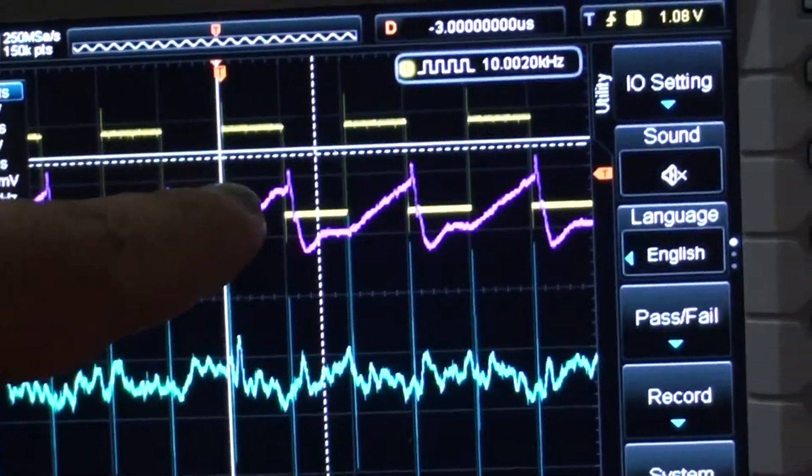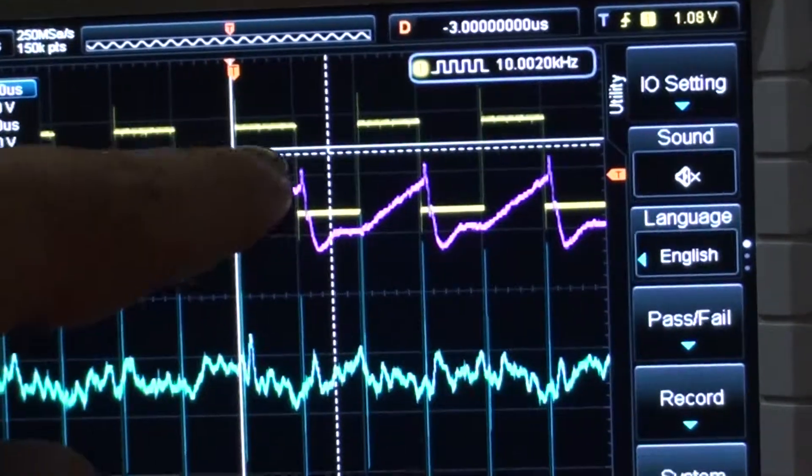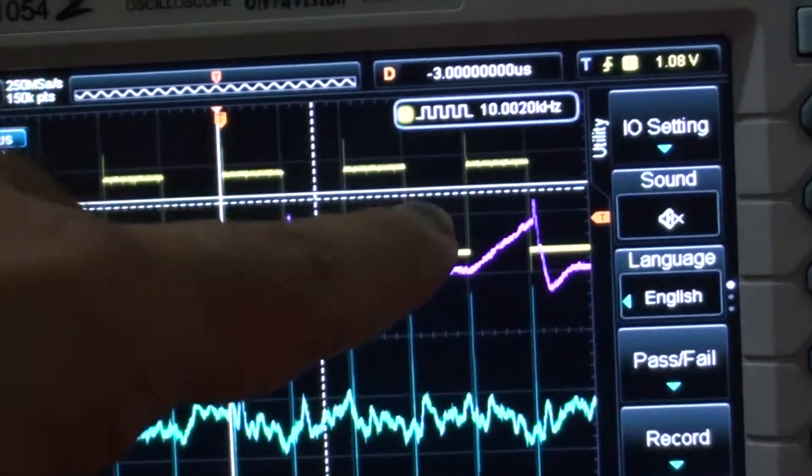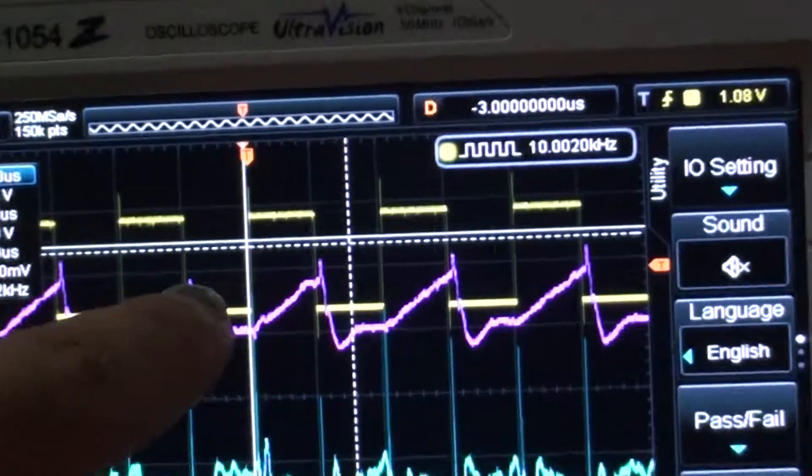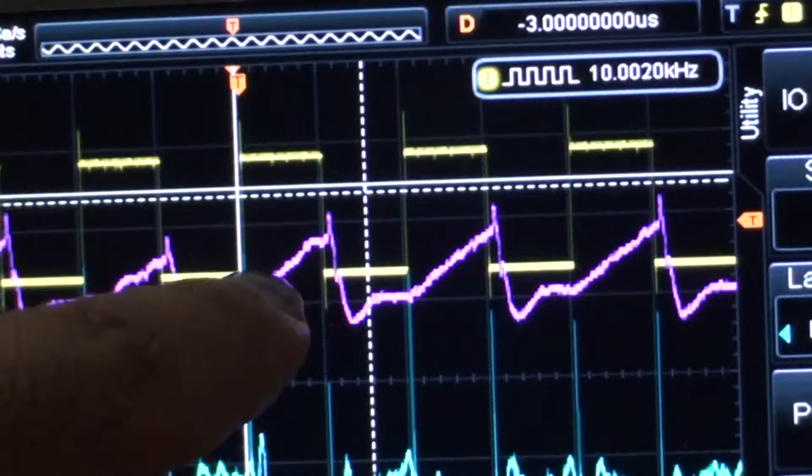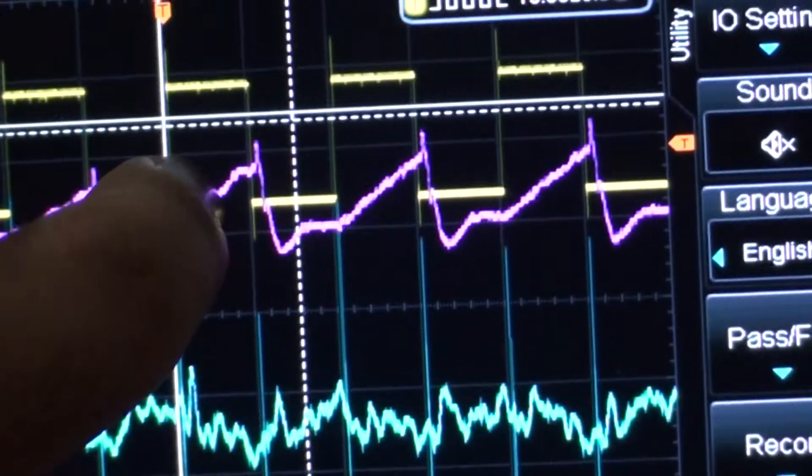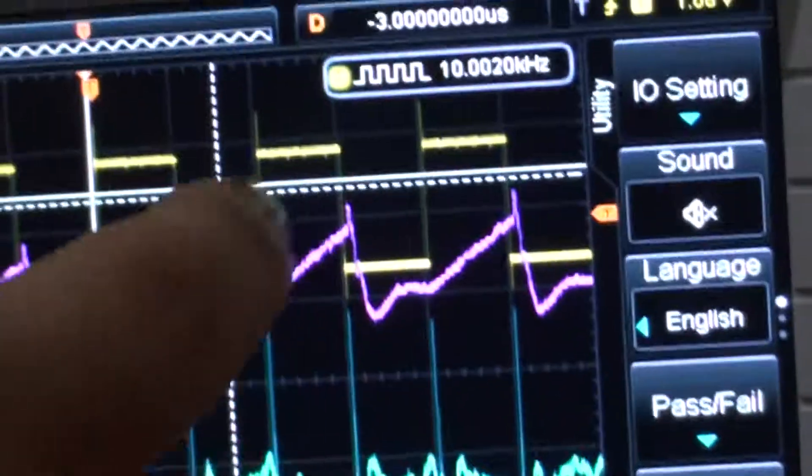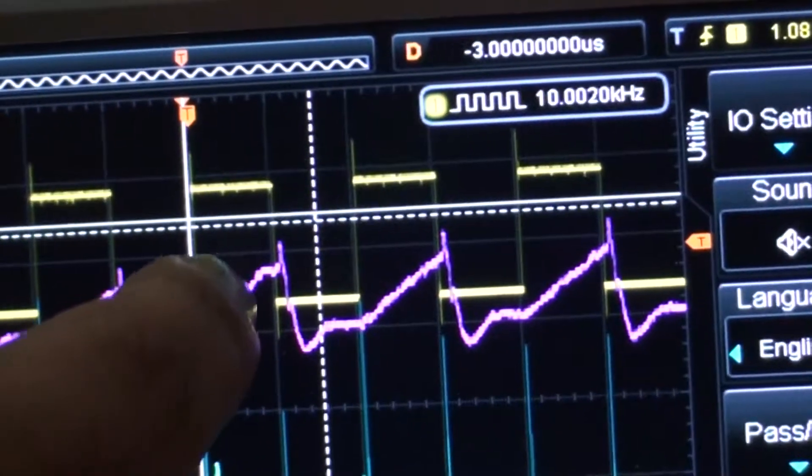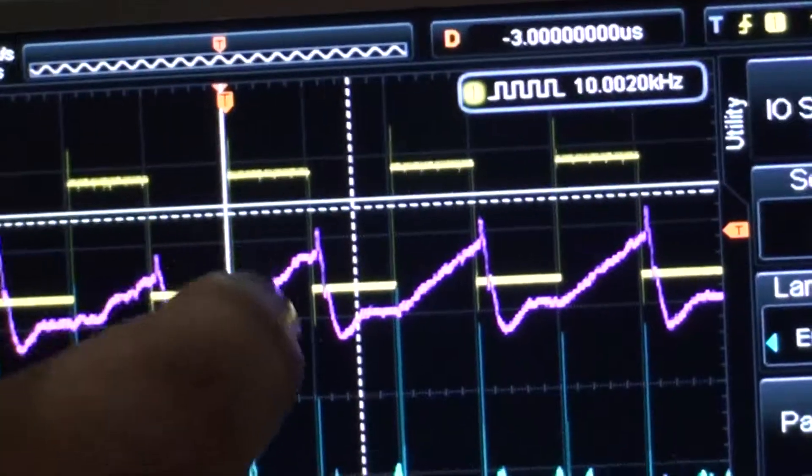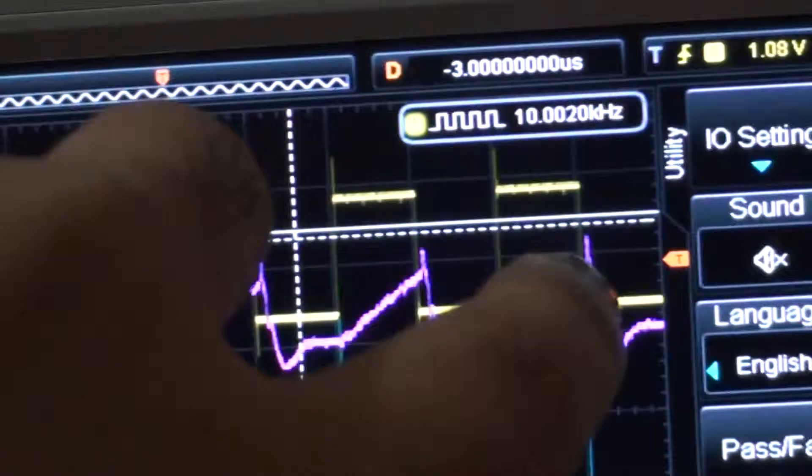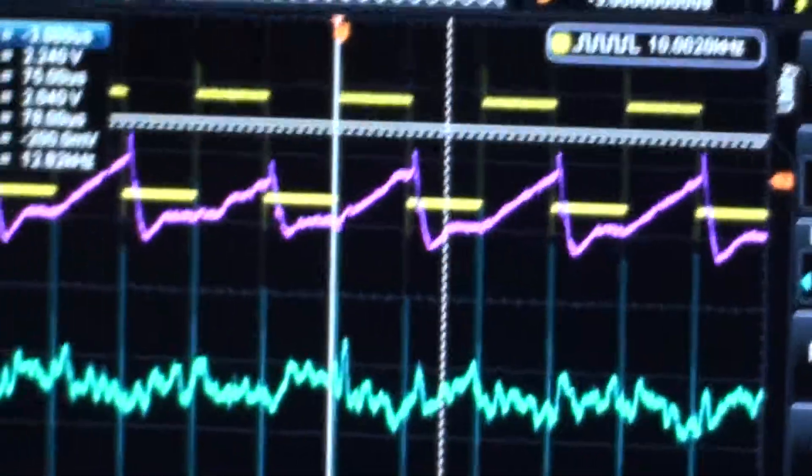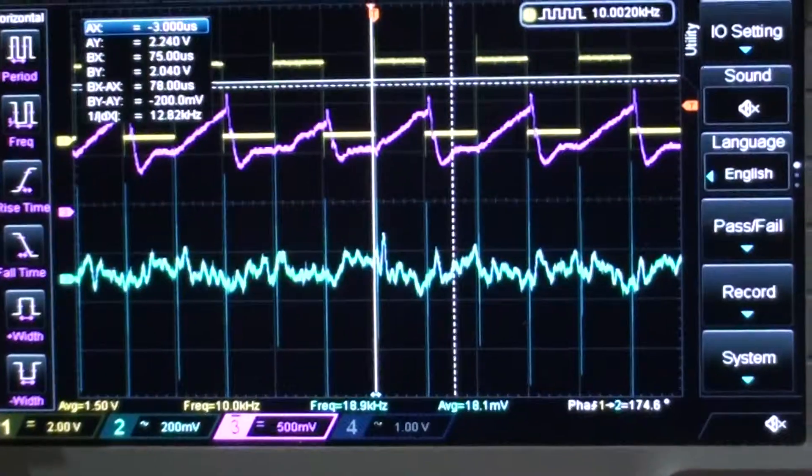Now how do you eliminate the noise or eliminate the PWM frequency that is riding on this, going up and down? Typically we do a synchronized measurement—that is, the measurement is done somewhere in the center, right at this point. If you synchronize the current measurement with respect to PWM somewhere in the center of the PWM on-time, then you will measure only the center point, which typically is the current seen by the motor.